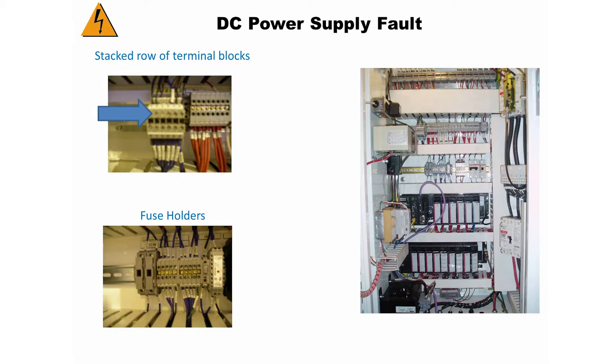There are four wires in each cable, so there are four rows of wires. The front wire is black — it is the signal wire back from the PROX switch. The color of the wire behind the black is either brown, which is the positive wire, or blue, which is the negative wire. The color of the wire does not make a difference because we will remove one wire at a time from the terminal block. At this time, do not worry about the clear colored wire.